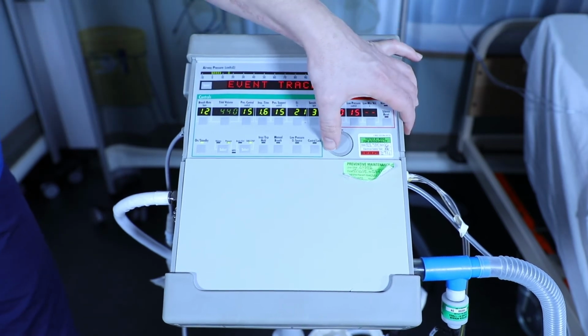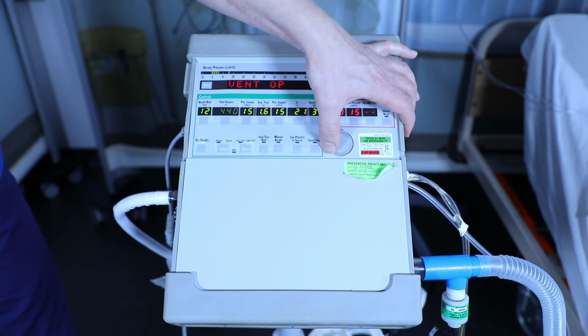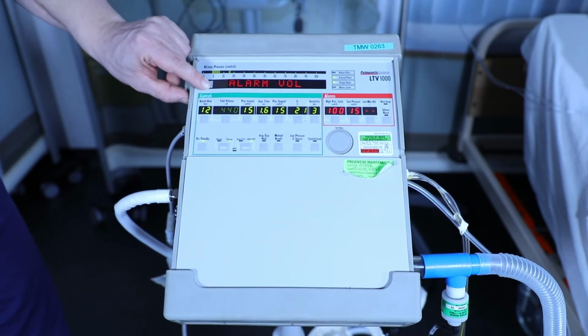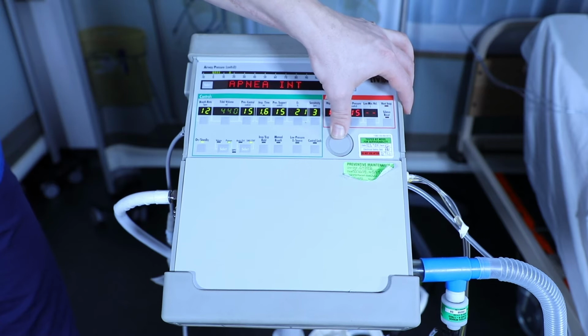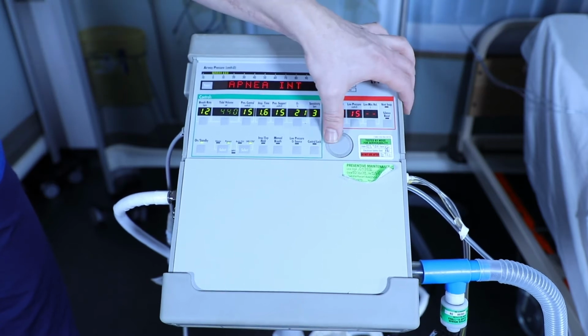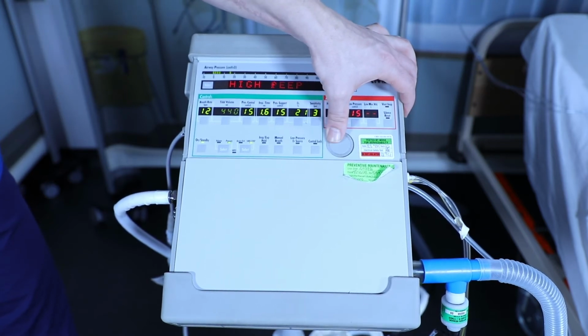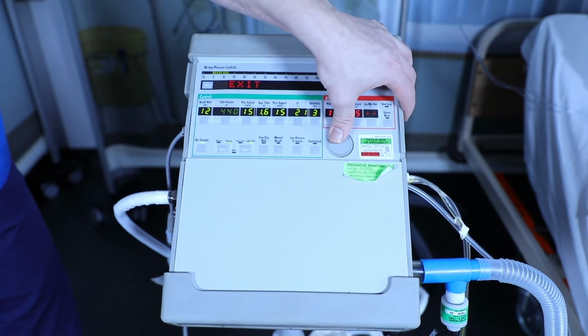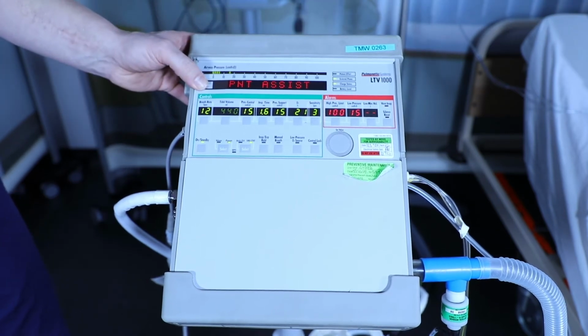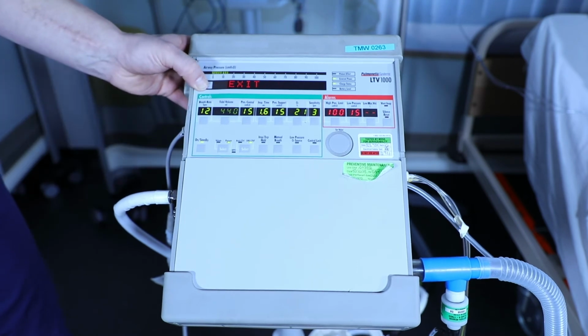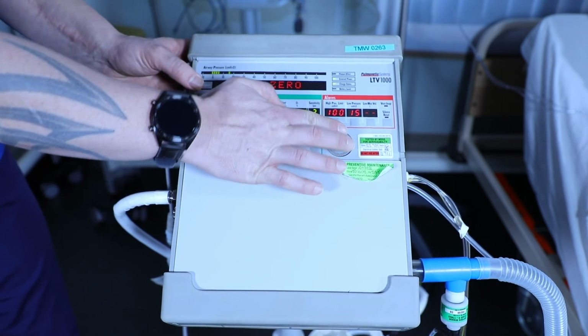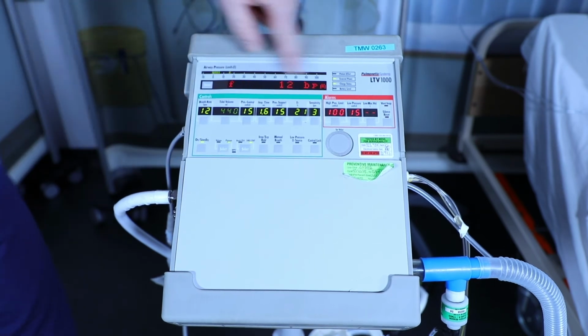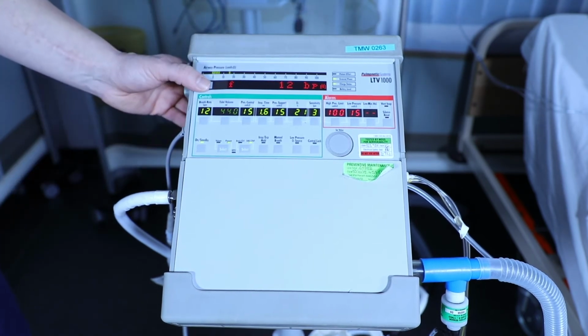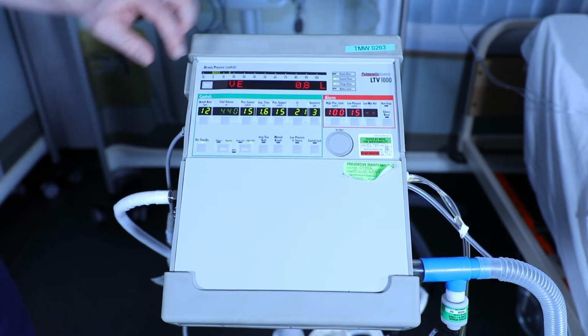We can also set our alarm settings, our apnea settings, high frequency and our high PEEP, should they be required for our patients. To come out of this, we want to go to exit and then continue to the exit again. And again, we'll now scroll through. If we double press on the select button, this returns to the scroll.